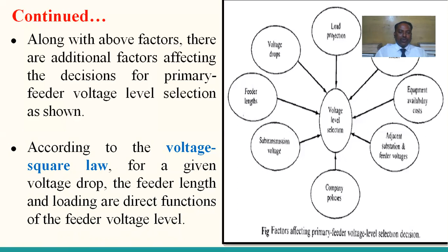So therefore, if the feeder voltage is doubled, for example, if 11 kV is there on the primary feeder and the voltage is to be doubled, how much load and how much area can be covered compared to the existing one? This is more important for us. For example, if the feeder voltage is doubled for the same percent voltage drop, it can supply power 4 times the distance, 4 times the distance.